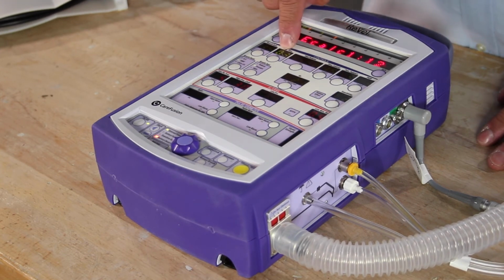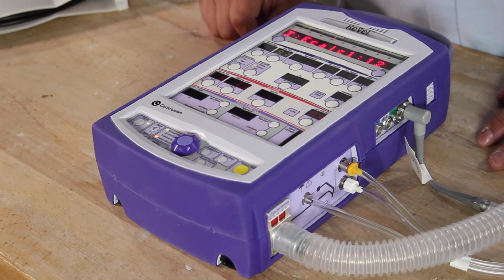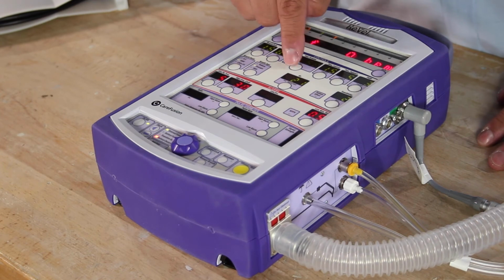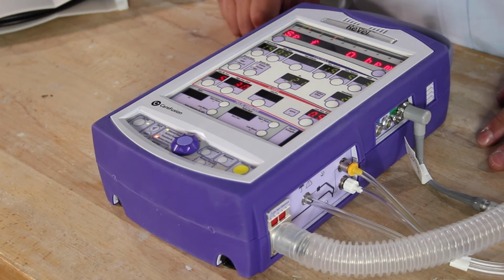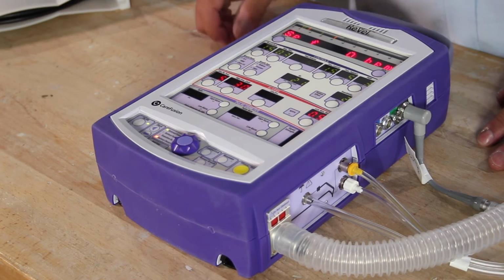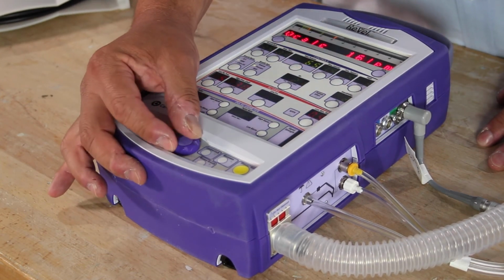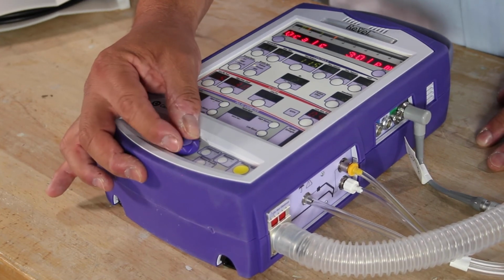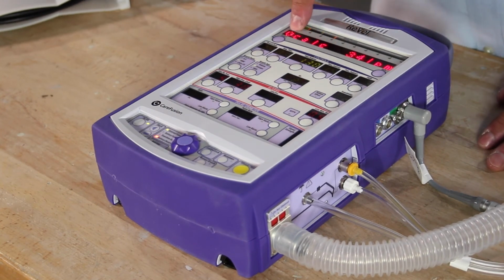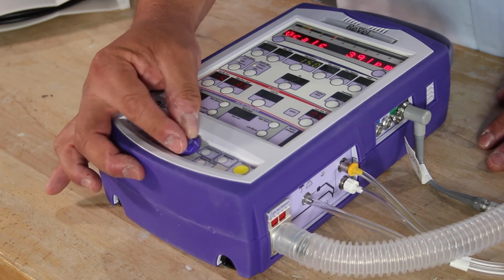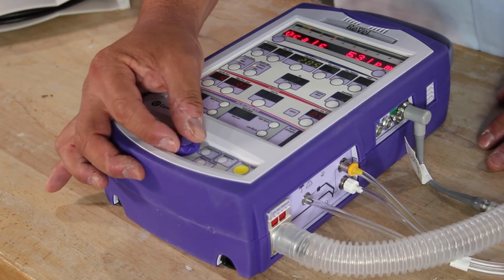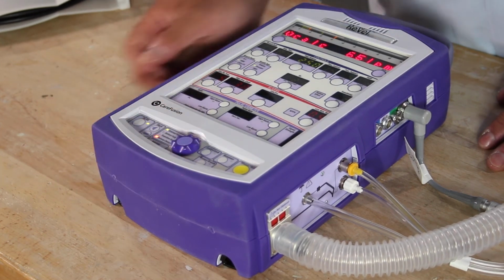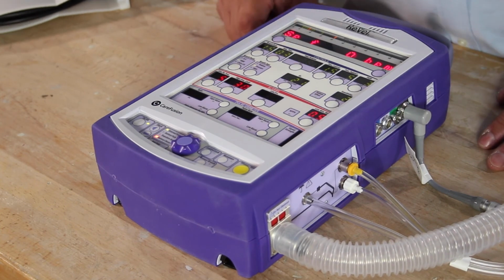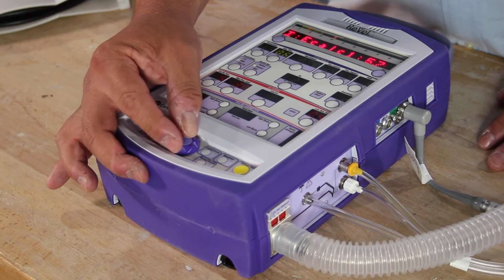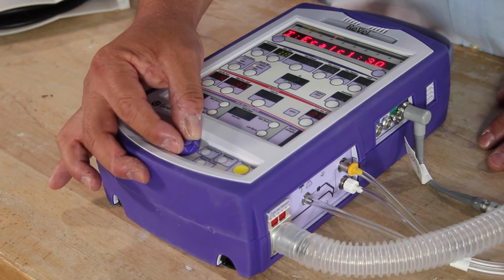So in order for me to change my I time, I have to increase the amount of flow that the ventilator will allow me to do. Even though we're not currently using the tidal volume feature, because we're in a pressure control mode of ventilation, I highlight the dimmed tidal volume and increase the amount of flow. How do I know how much flow? As I'm increasing my tidal volume, calculated flow comes up and shows me how much flow I'm increasing to. So I'm just gonna move this up to, let's say, 250. Okay, I'm gonna hit select. And now to increase my I time, press, which also changes my I time and my I to E.